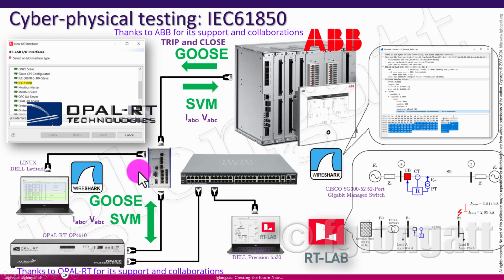The sample values go into an industrial switch, and we can use sniffer software like Wireshark to monitor the data and packet flow inside the network. These sample values go into the digital relay, representing the three-phase voltages and currents, and with that the relay is able to perform automation, control, and protection activities.